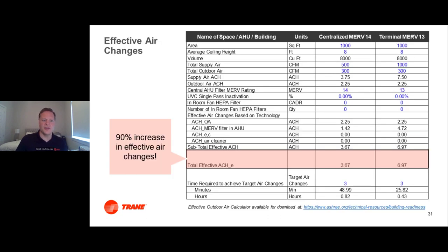But if you actually do a comparison, and what this is pulled from is a tool from ASHRAE called the Effective Outdoor Air or Effective Air Change Calculator. And this is a way of calculating how many effective air changes am I getting, and it gives you credit for the filter. So if you notice the centralized MERV 14, I'm at 50% supply airflow. A lot of our systems are going to be designed for minimum airflow in a VAV box to turn down at least 50%. That's a code requirement.